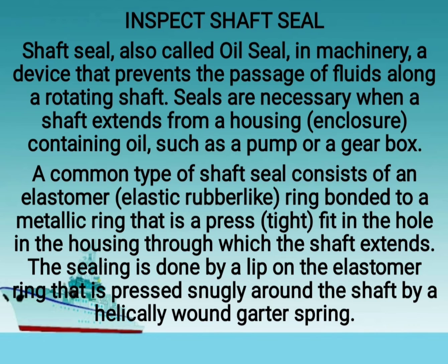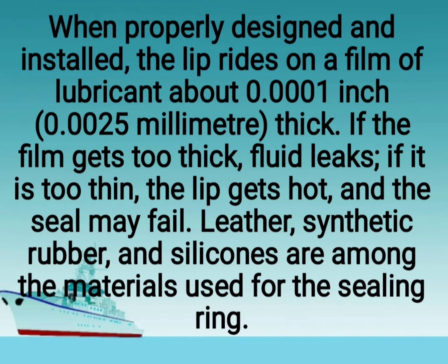The sealing is done by a lip on the elastomer ring that is pressed snugly around the shaft by a helically wound garter spring. When properly designed and installed, the lip rides on a film of lubricant about 0.0001 inch, 0.0025 millimeter thick. If the film gets too thick, fluid leaks. If it is too thin, the lip gets hot and the seal may fail. Leather, synthetic rubber, and silicones are among the materials used for the sealing ring.